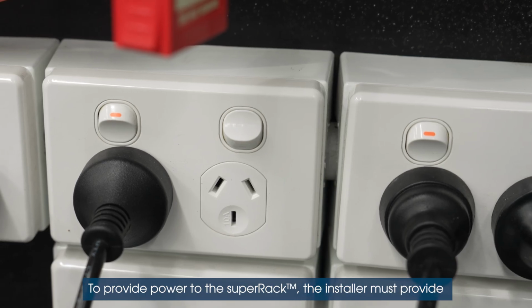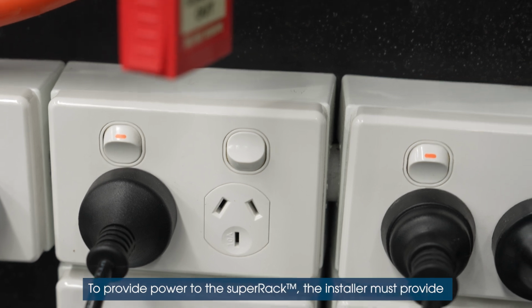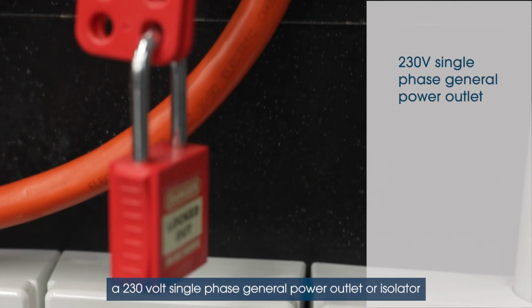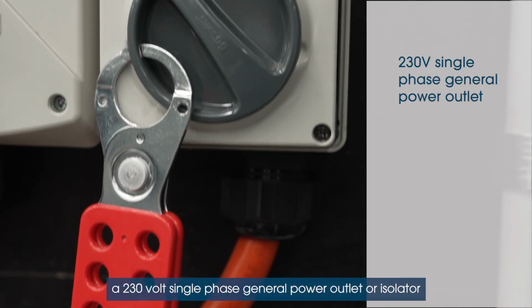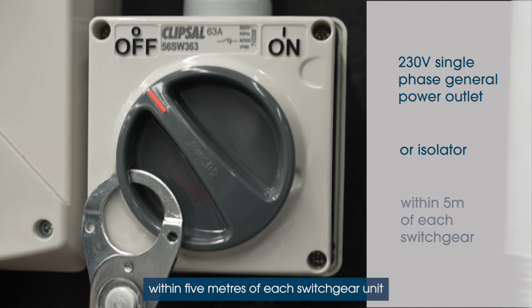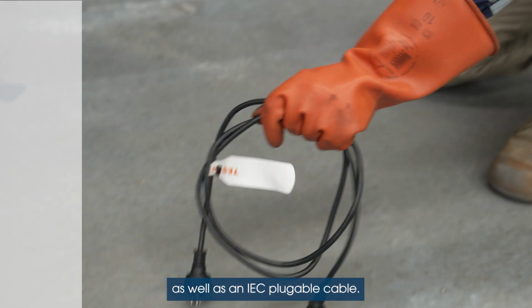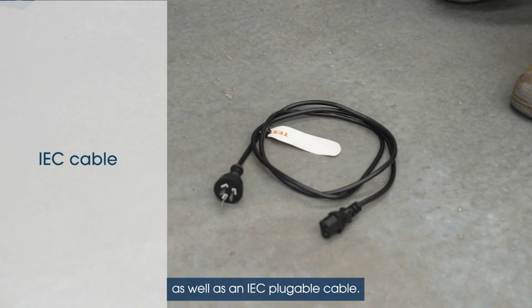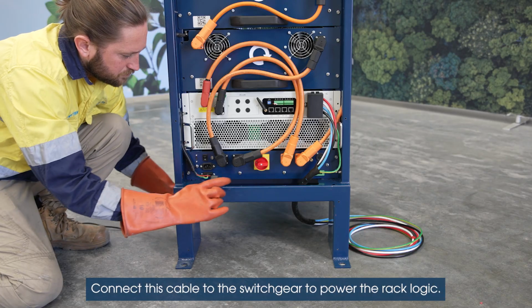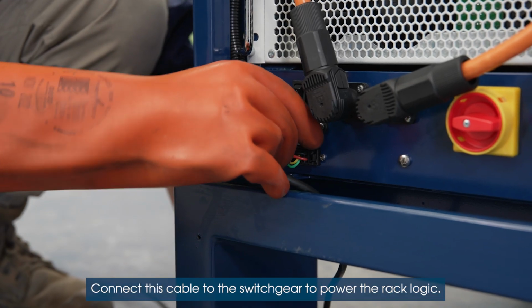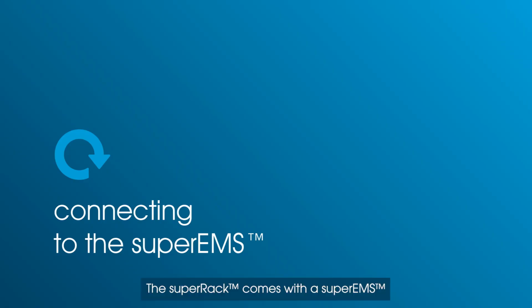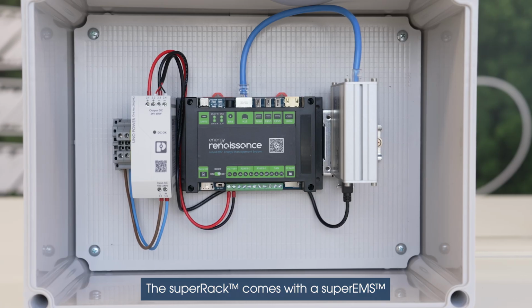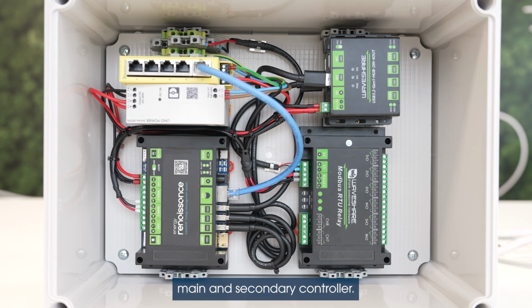To provide power to the superRack, the installer must provide a 230 volt single-phase general power outlet or isolator within 5 meters of each switchgear unit, as well as an IEC pluggable cable. Connect this cable to the switchgear to power the rack logic. The superRack comes with a superEMS main and secondary controller.